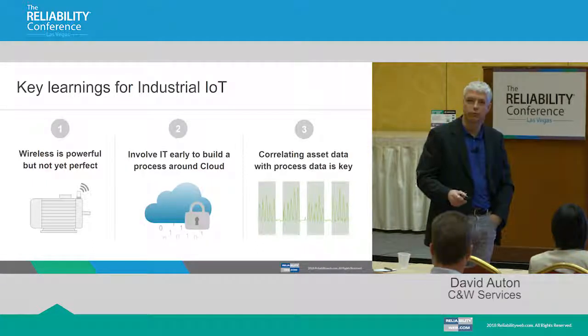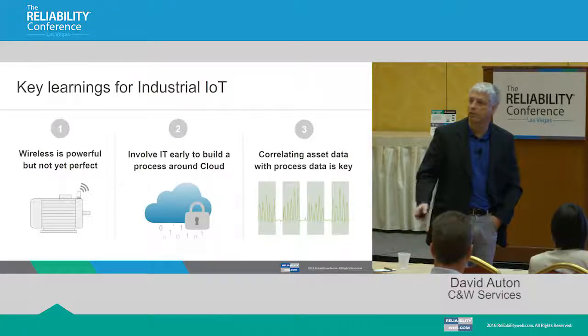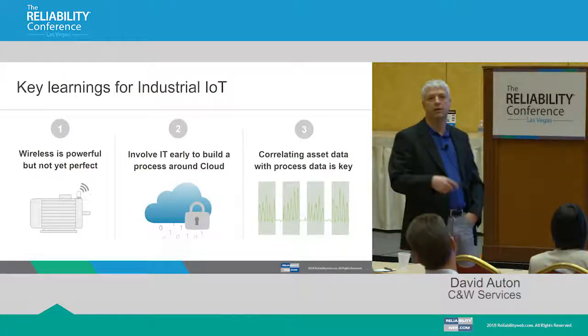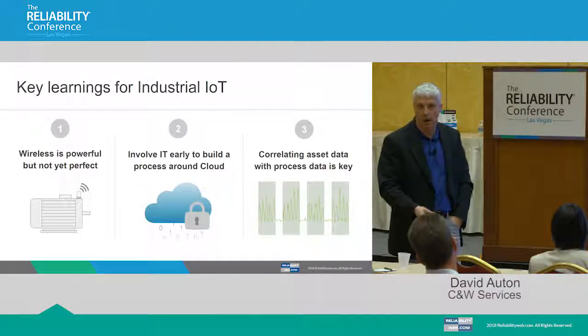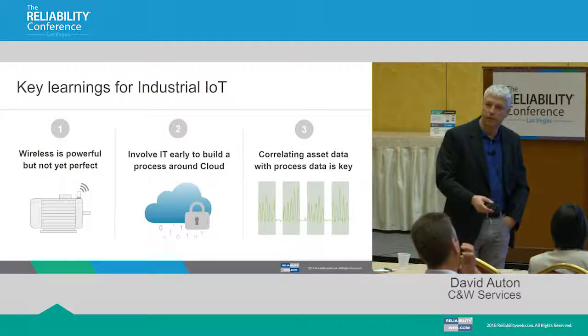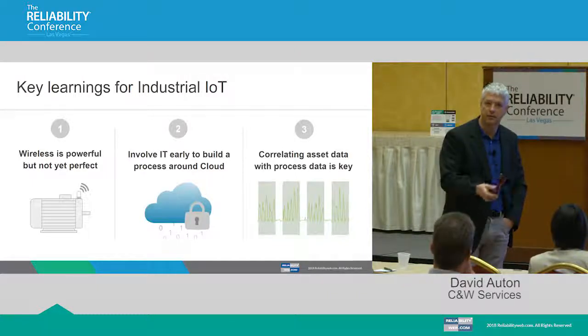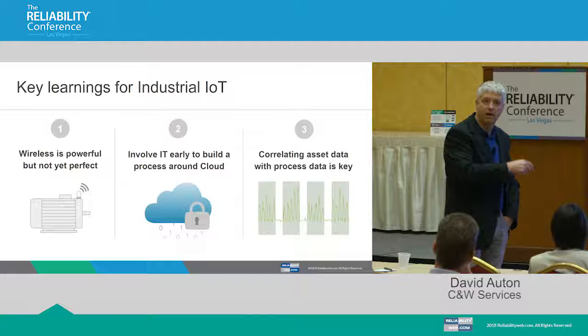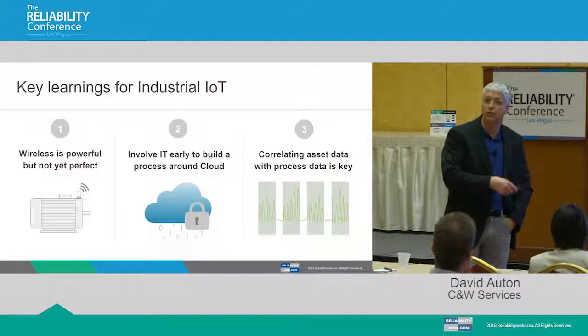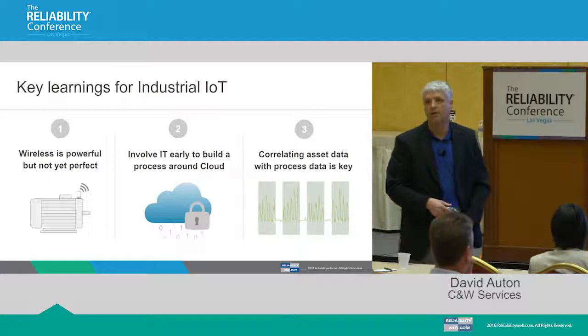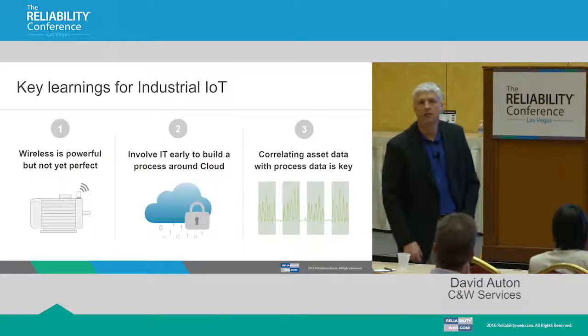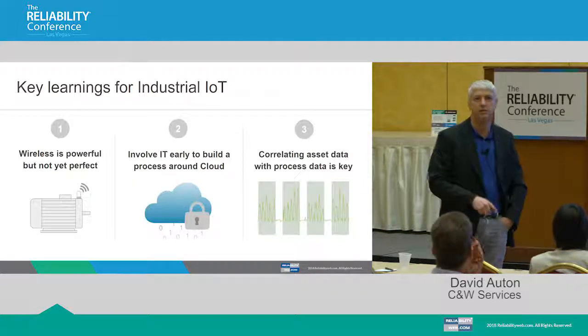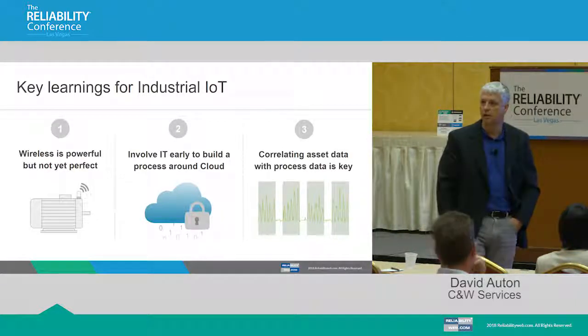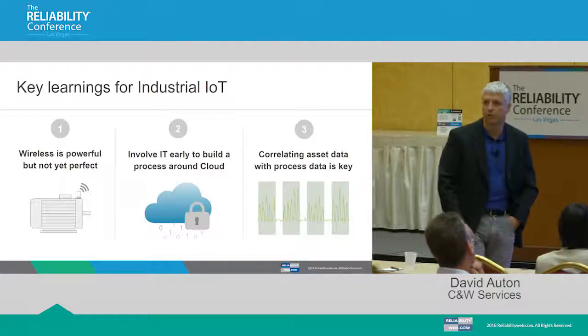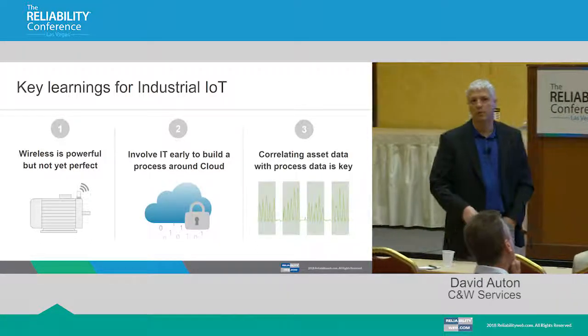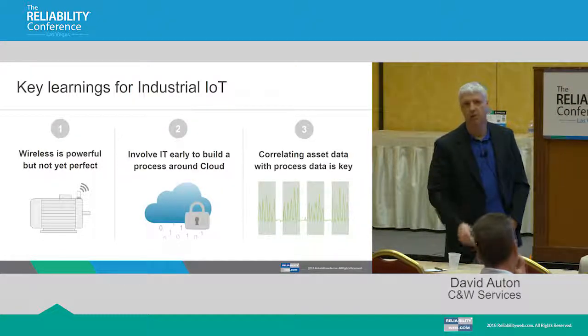So the two things: one is he's not trying to look at 25 different screens to figure out what's going on, and they don't have to necessarily diagnose the problem, they just need to be able to triage it, right? So if you see a drop in air pressure and you start seeing BAS alarms for the VFDs, and then you start seeing temperature or vibration going on all at the same time, you can almost say, okay, my motor's hosed, and triage that much faster with the more information you have. So think in long terms of how I'm going to use this information with the rest of the information that's coming in, and the particular people who are using and consuming that information, how that's going to help them perform their job both better and, more specifically, more efficiently, right?